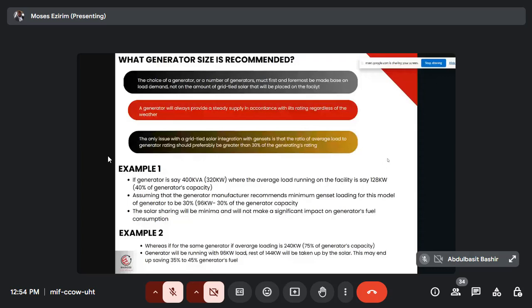Now, the generator will always provide a steady supply, while solar depends on the weather and your inverter capacity. What happens if the weather is not friendly? That means there will be an overload, and your system will be short. Now the only issue with a grid-tied solar integration with genset is average load. The average load should preferably be greater than 30% of the generator rating.